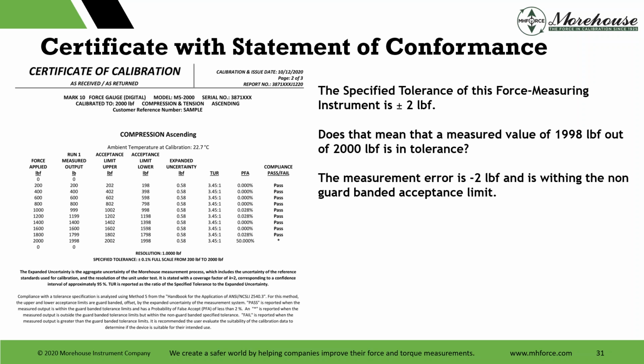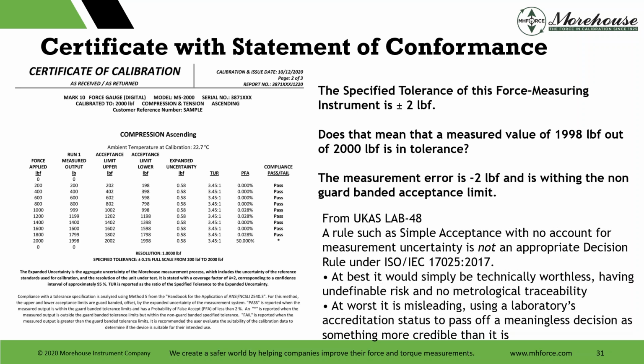Here's where some people would say, simple acceptance, okay, we could still say pass. But there is this other standard that's gaining popularity, and it's UKAS LAB 48, and it says a rule such as simple acceptance with no account for measurement uncertainty is not an appropriate decision rule under ISO IEC 17025:2017. At best, it would be simply technically worthless, having an undefinable risk and no metrological traceability. At worst, it is misleading, using a laboratory's accreditation status to pass off a meaningless decision as something more credible than what it is. And that's true.